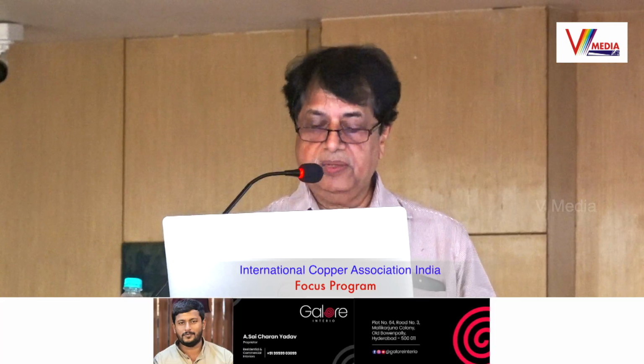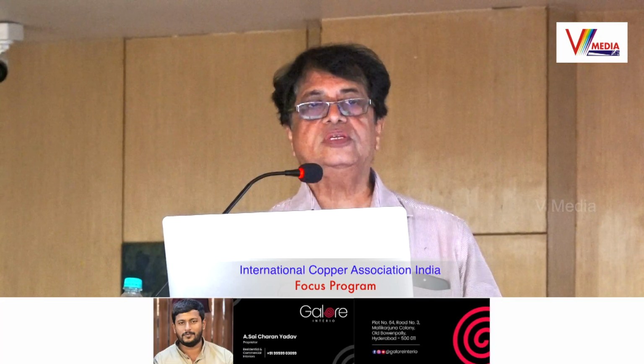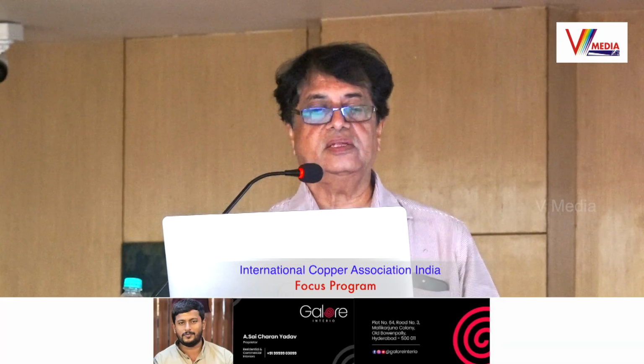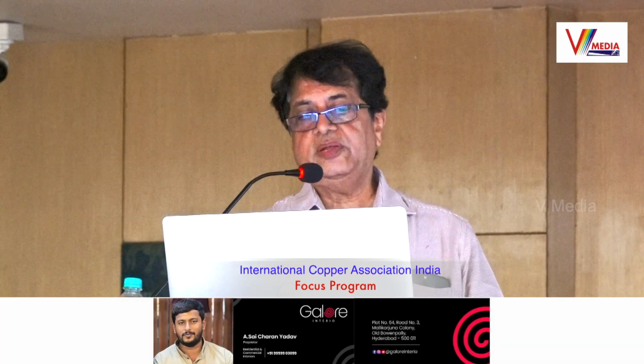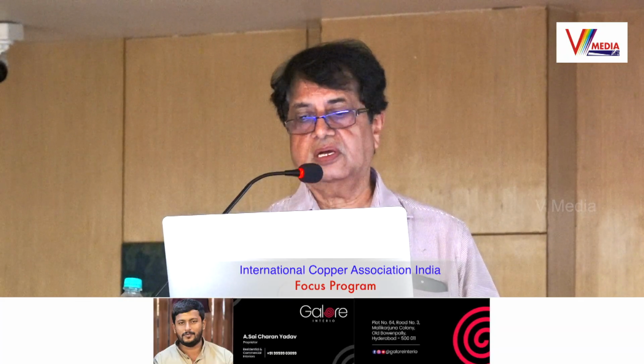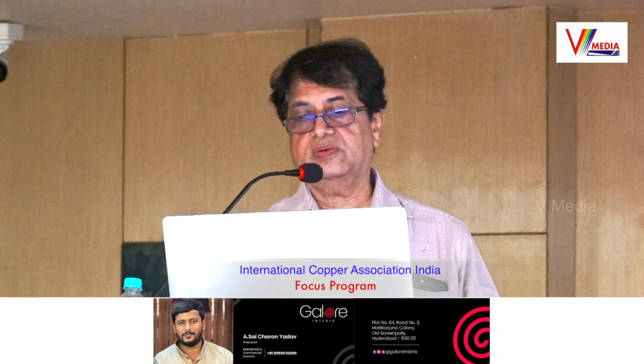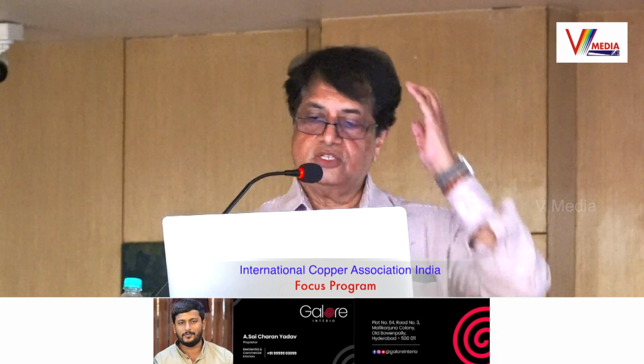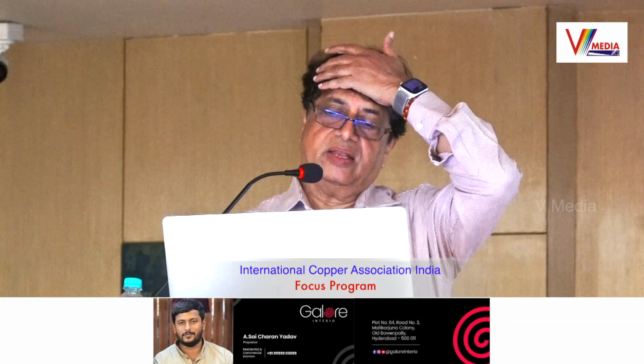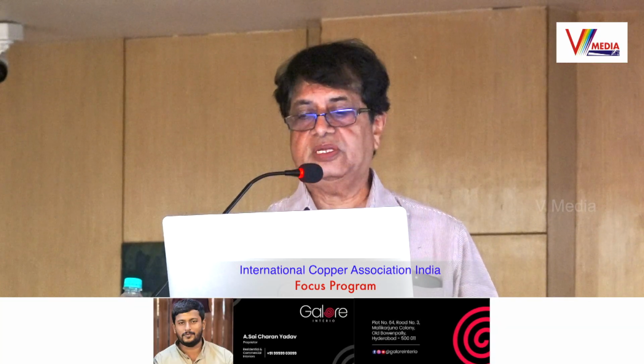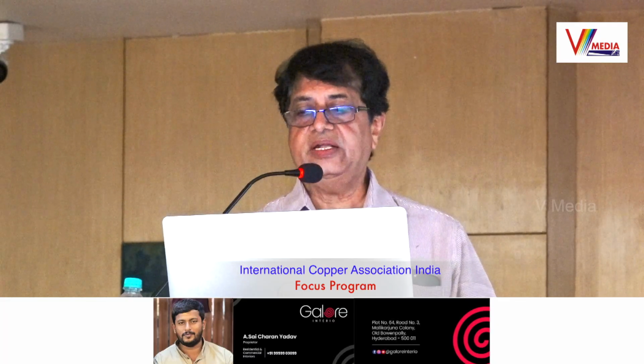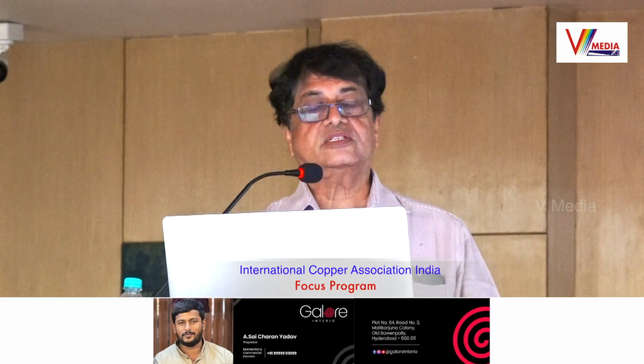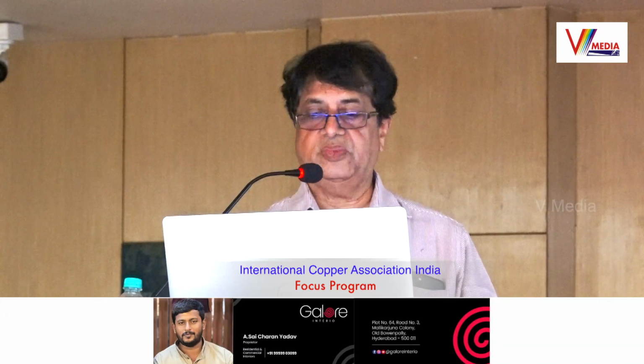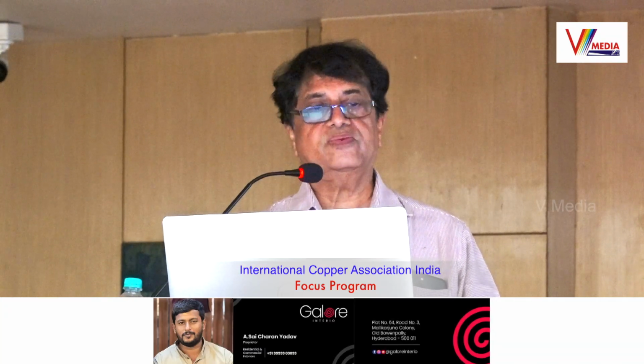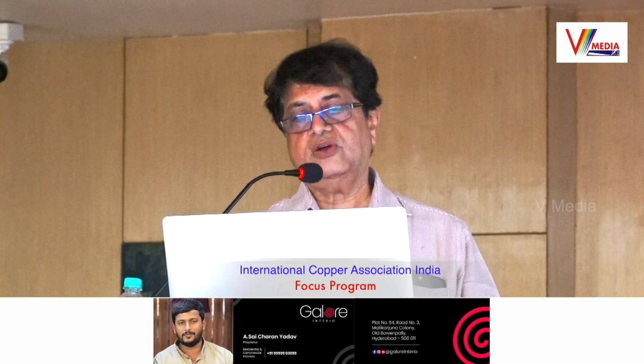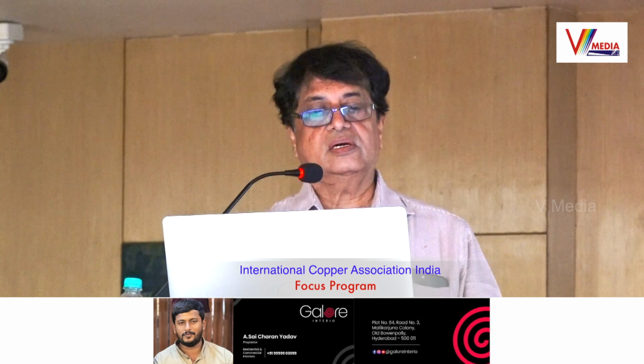So this is one of the standards showing how much clearance you have to maintain from the transformer substation and the adjacent structure. The detailed calculations depend on the content of the oil and on the structure which is adjacent to your transformer. There are two classes defined. One is the load bearing system, which they call REI, and one is EI, the non-load bearing type system. R is the load bearing capacity, E is the fire integrity, and I is the thermal insulation, that is 60 or 90 minutes, which refers to the fire resistance duration in minutes. In part 3, section 22 of the National Electrical Code, the details are mentioned, and in accordance with that you have to maintain the clearance around the transformer.